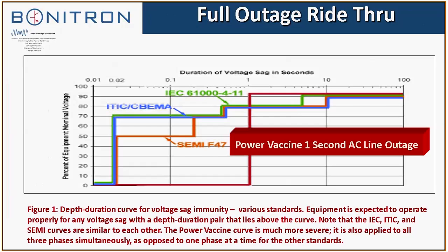Now, a little bit more about full outage ride-through. Usually you're talking about a 1 to 2 second full outage. Samsung has a 1 second requirement, which is above and beyond most of the other industry requirements for ride-through. And as I said, if you have specified a SAG ride-through, and the customer finds out there are full outages, we can retrofit the SAG ride-through with up to 2 seconds of full AC line loss protection. This matches a lot of the other industry specs that are out there right now. Actually, the UltraCap ride-through was a result of the Samsung specification.